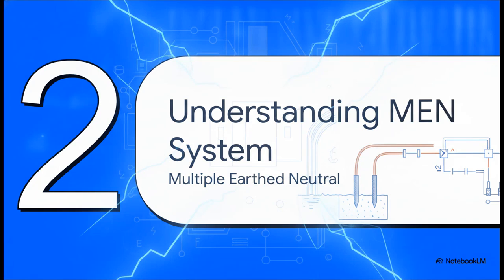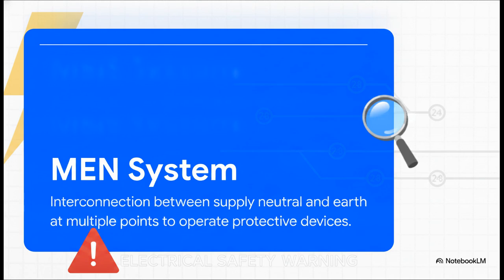Moving on to Section 2, understanding the MEN system. To properly and safely dismantle a system for testing, we first have to understand exactly how it was built to protect us in the first place, right? The MEN, or multiple earth neutral system, relies on an interconnection between the supply neutral and the mass of earth at multiple points. If a fault happens, this link ensures that enough fault current flows to earth to rapidly trip your protective devices.